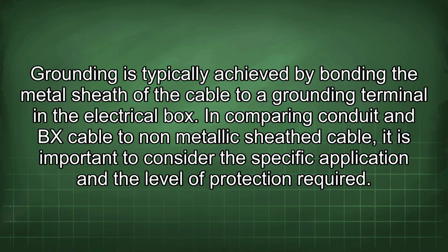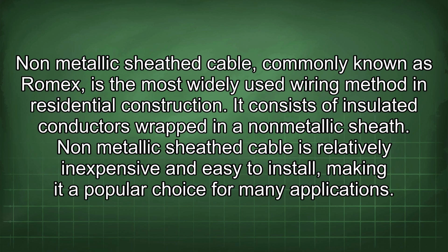In comparing conduit and BX cable to non-metallic sheathed cable, it is important to consider the specific application and the level of protection required. Non-metallic sheathed cable, commonly known as Romex, is the most widely used wiring method in residential construction. It consists of insulated conductors wrapped in a non-metallic sheath. Non-metallic sheathed cable is relatively inexpensive and easy to install, making it a popular choice for many applications.